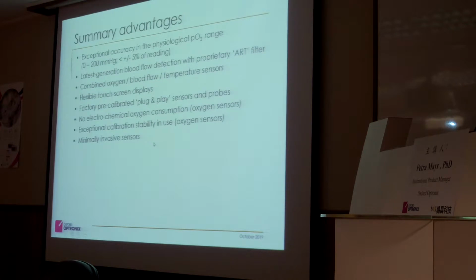The sensors are minimally invasive, which means the oxygen sensor has to be in the tissue. It can't be outside, because then you measure atmospheric oxygen. So it has to be inside, but because it's very small, it's minimally invasive. Also the sensors without the temperature are MRI compatible, because they don't have any metal. So we make 8-meter long cables. The sensors can go through the cable shaft into the magnet, and the instrument stays quite far away outside that Gauss curve. Okay.